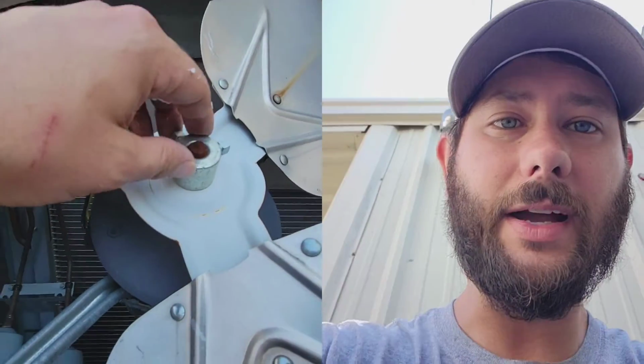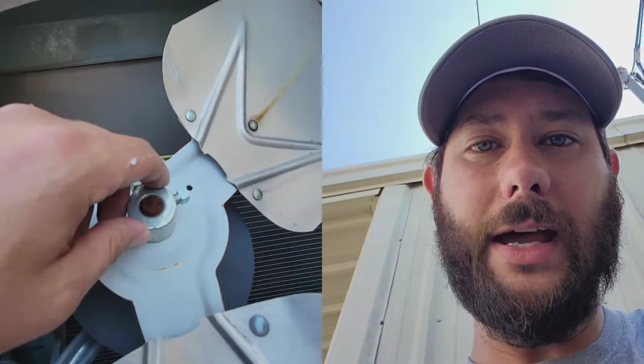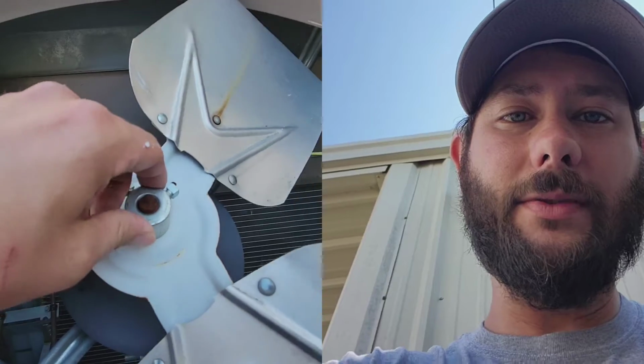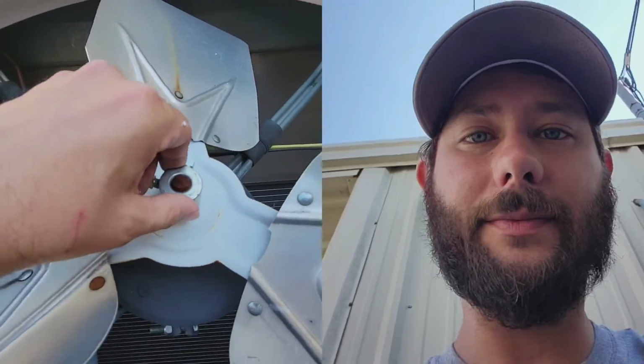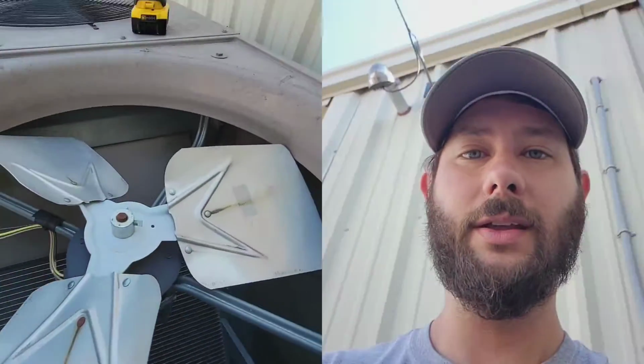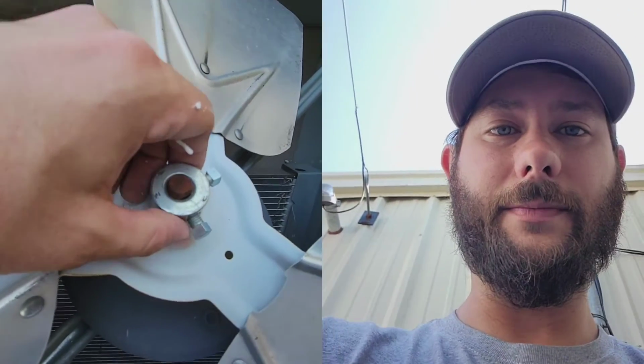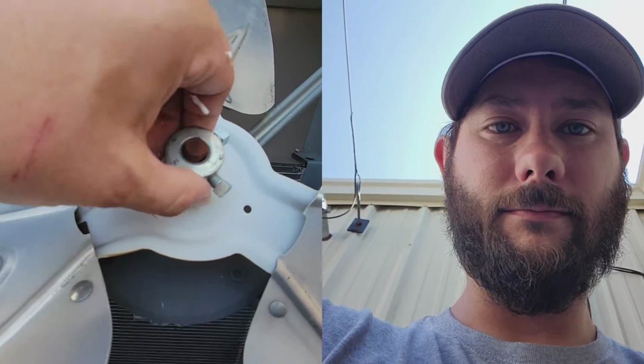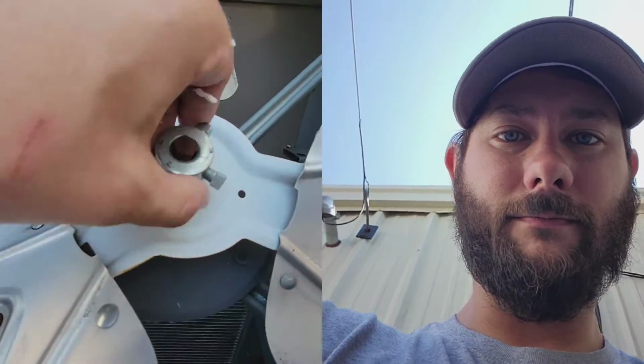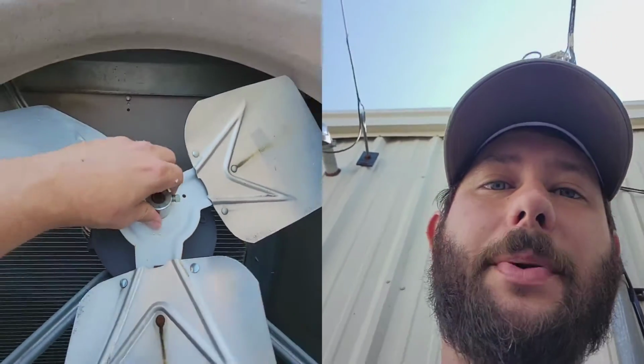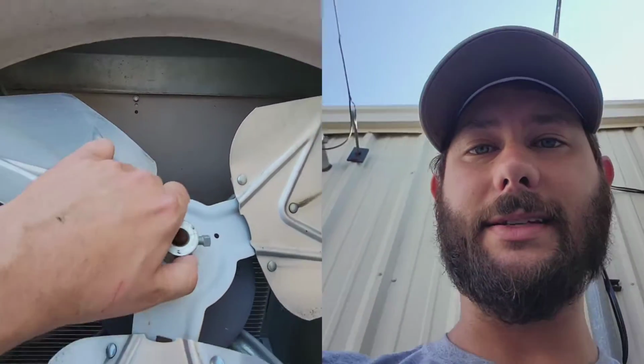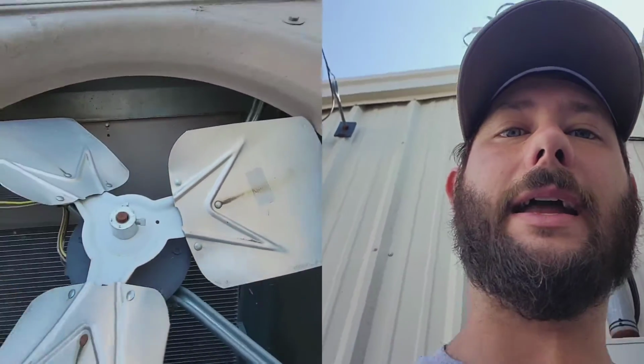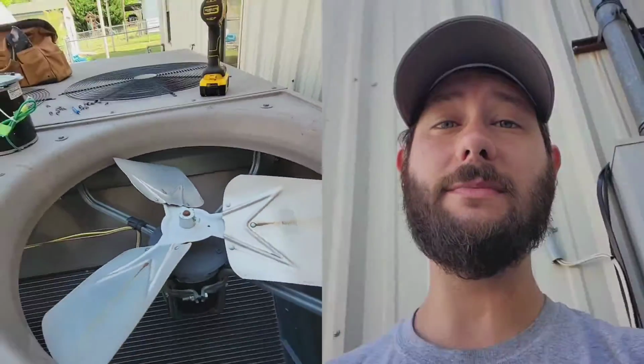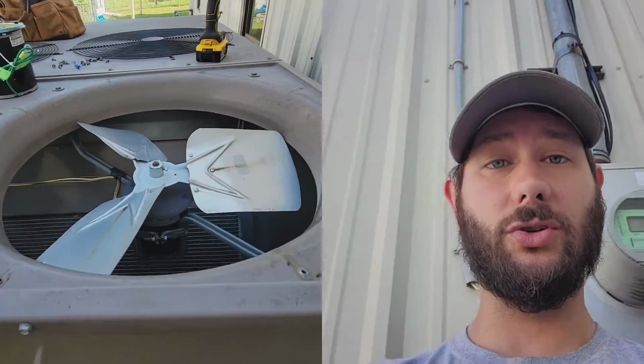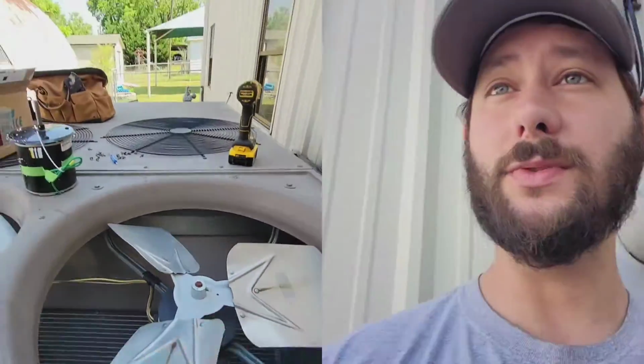Okay, this right here is a good motor. How do I know that? Because I can push it back and forth right here and there's no slack, so the bearings are good. Now up and down, you don't need to do that, just side to side. If it's got slack, then the bearings are possibly bad, so you want to make sure you check the bearings on the motor—that's what's wrong with this package unit.